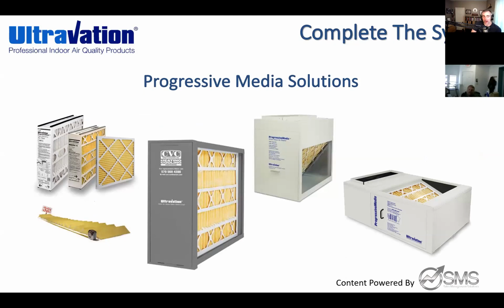As I hinted, we do high filtration. Meier Supply actually stocks our support boxes here. We color match them to the equipment, and we have MERV 11 and MERV 13 class filters, with 32 feet of pleated filter in our 5-inch filters. That's one reason we don't have pressure drop issues, because we give more surface area, so we don't have to weave them as tight. I have the graphs to back that up too for system design.